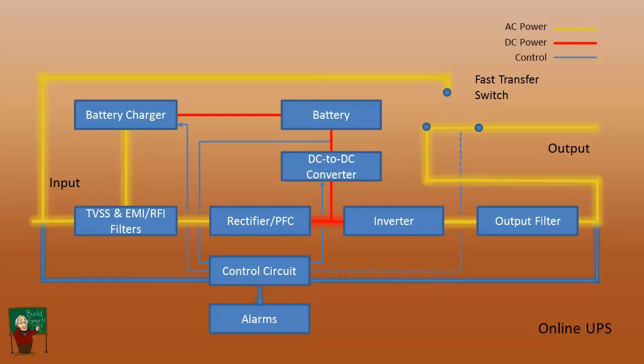Notice that all the voltage that's provided at the output is coming through the rectifier and inverter. So this one is constantly online. It's not just when the power goes out, but there's always that total isolation between the input and the output, and the whole input power is converted to output.